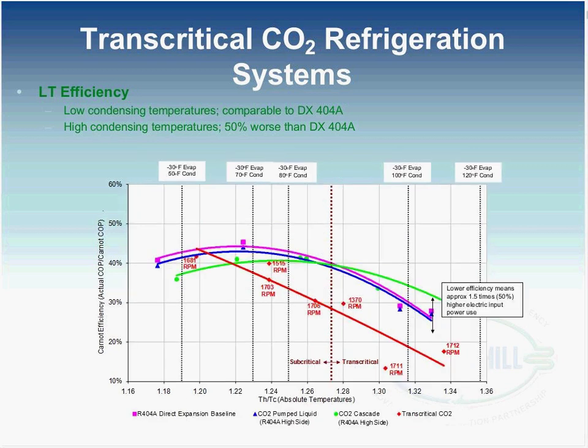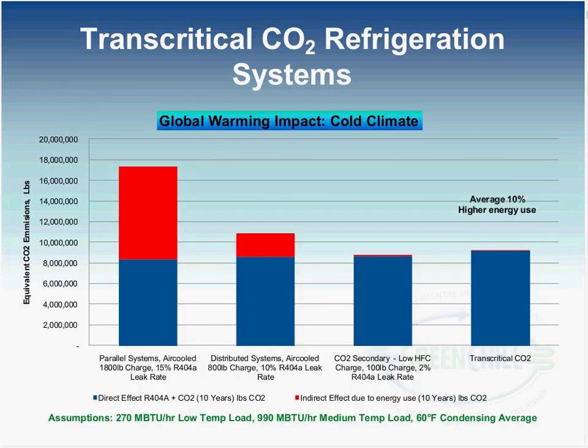Otherwise, on a low-temp system, we see similar results: in the transcritical mode and the higher pressure mode, the system is less efficient than the other systems, such as a cascade CO2 or 404A direct expansion system. But when you are down in the subcritical range and the low condensing temperatures of 50 to 70 degrees, you can get some comparable performance.